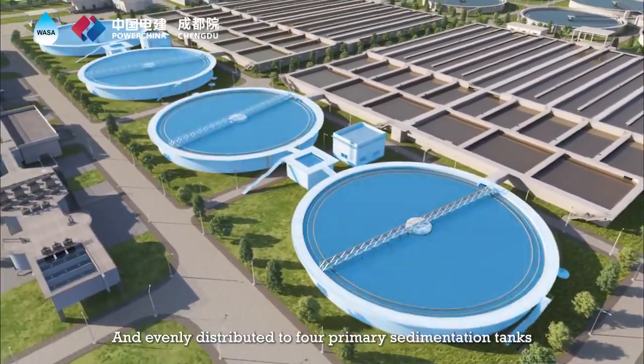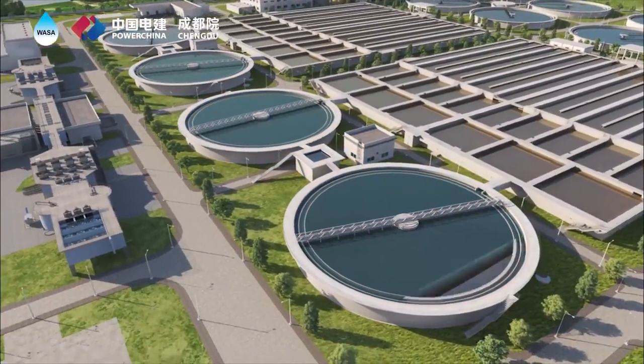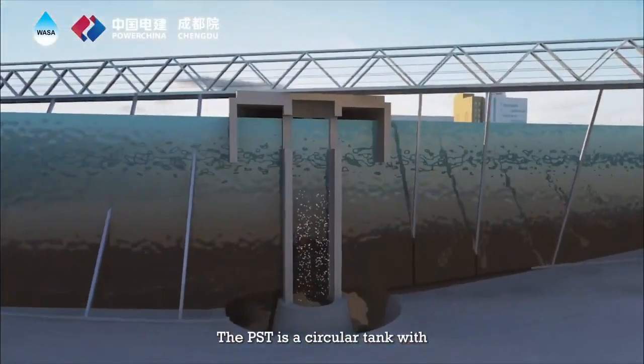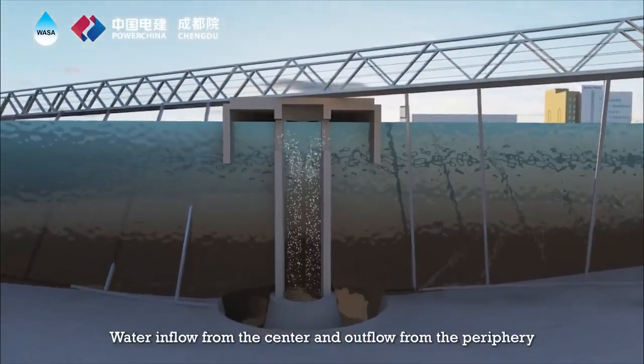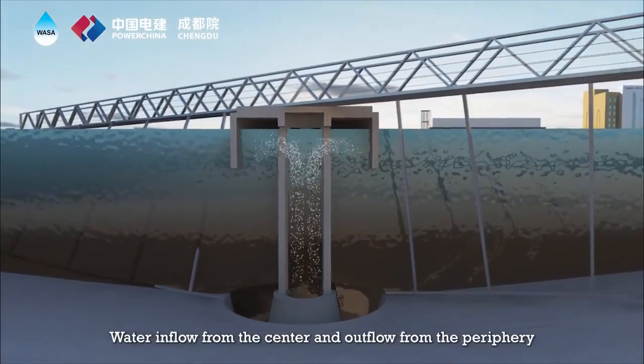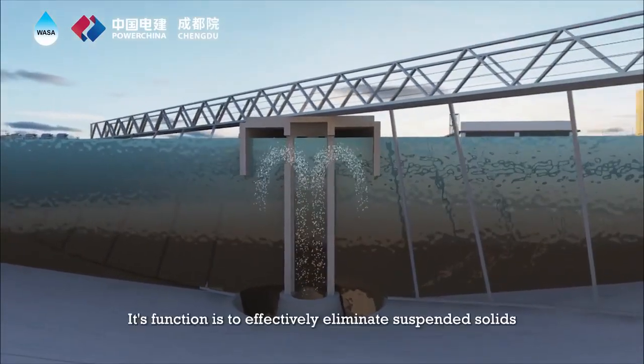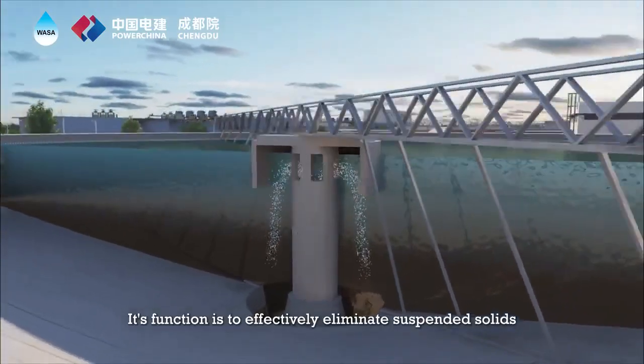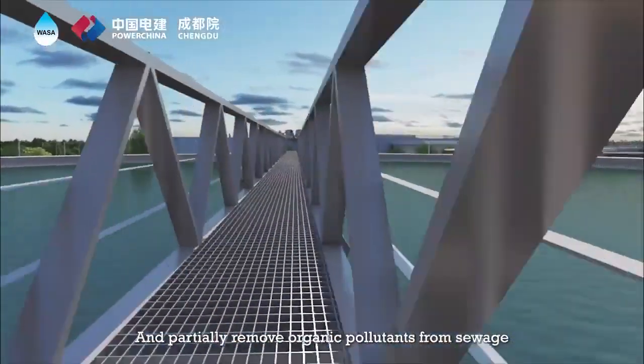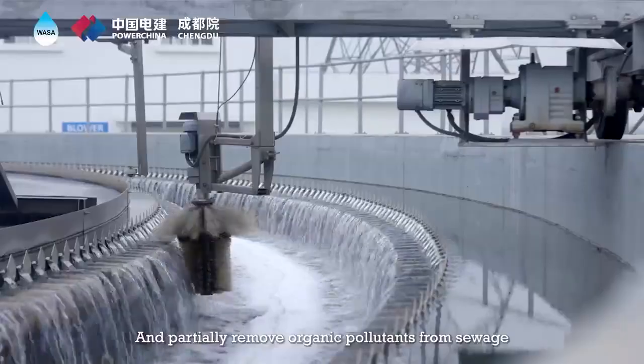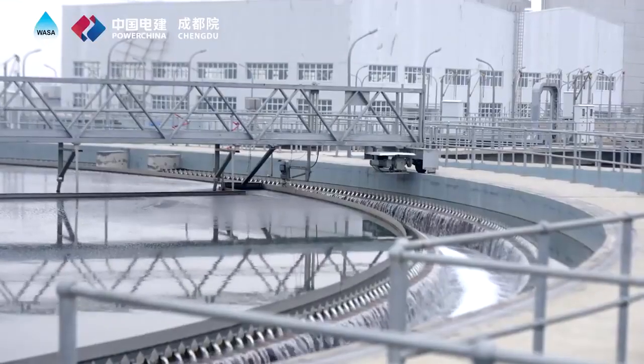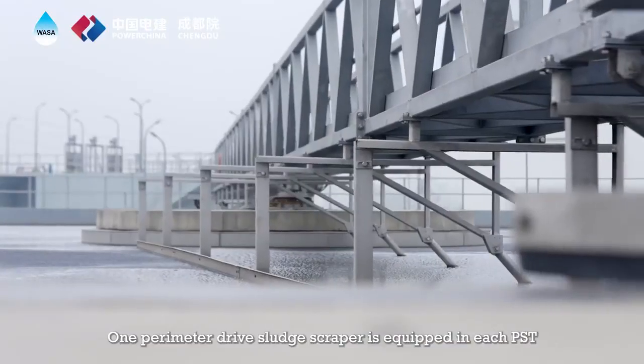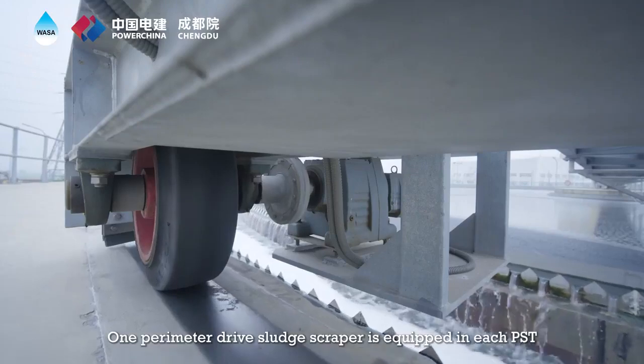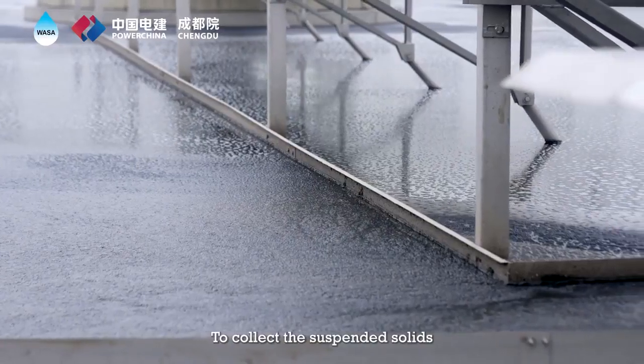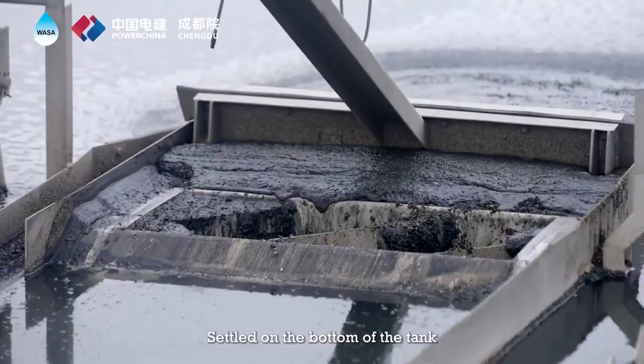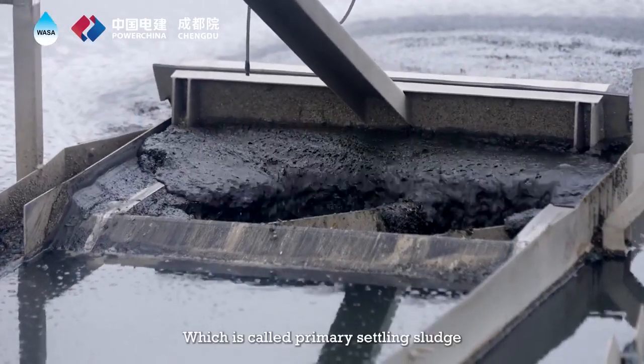4 primary sedimentation tanks. The PST is a circular tank with water inflow from the center and outflow from the periphery. Its function is to effectively eliminate suspended solids and partially remove organic pollutants from sewage. 1 perimeter drive sludge scraper is equipped in each PST to collect the suspended solids settled on the bottom of the tank, which is called primary settling sludge.